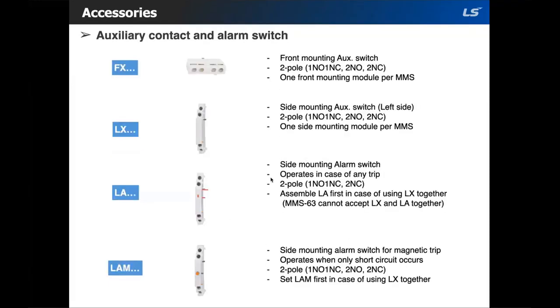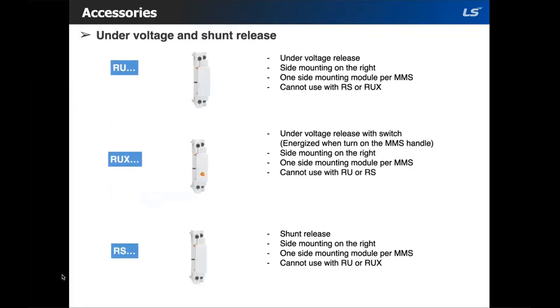And the LAM serves the same function as the LA, but this would be for the magnetic trip only, so when it's tripped on short circuit. And it's also stackable with LX. L means it's on the left side, so all these are on the left side of the MMS. And then on the right side, you could use an undervoltage release. You can only mount one per module, and these you cannot stack. And then RUX would be your undervoltage release with switch. Just like the RU, you cannot stack them, and you can only use one per module.